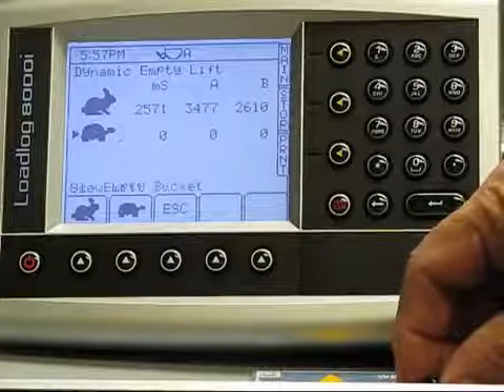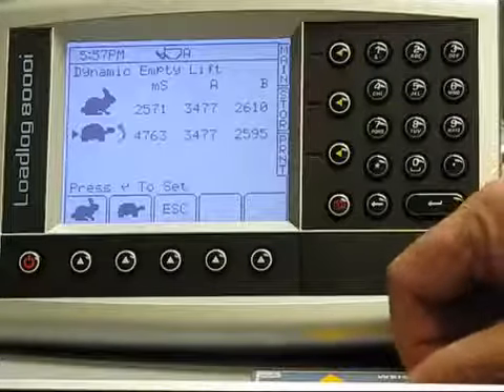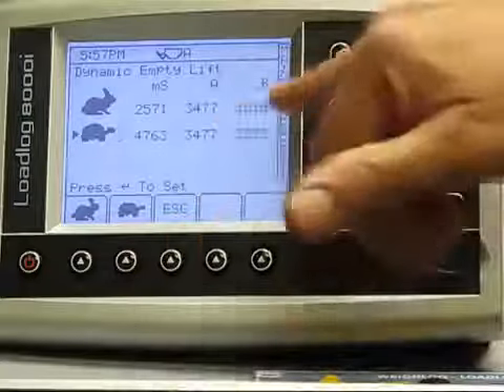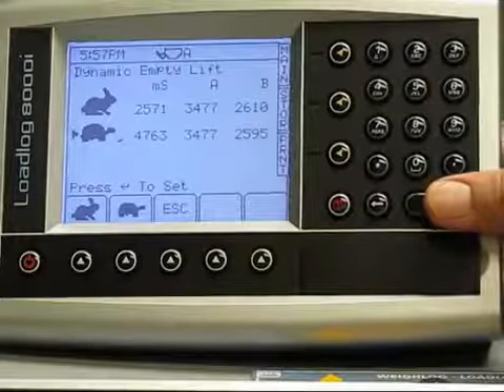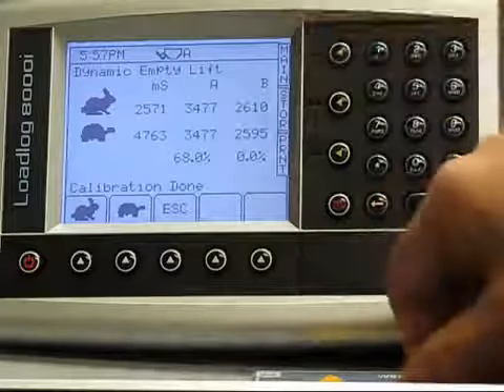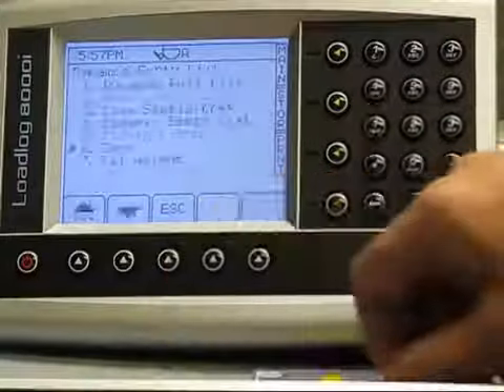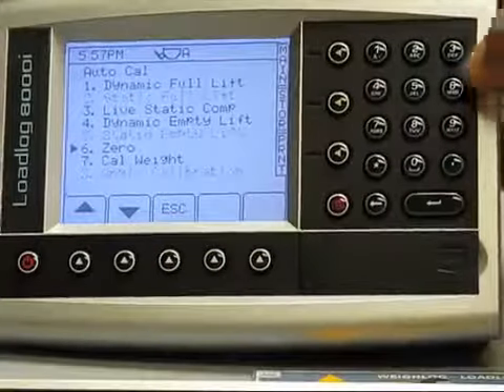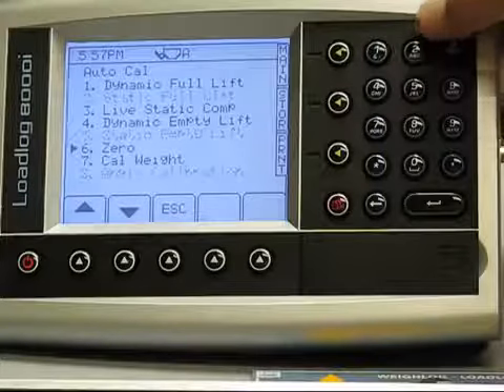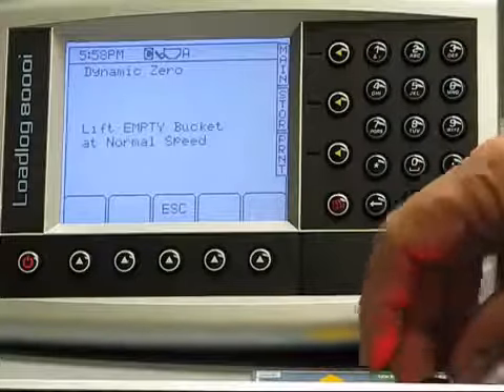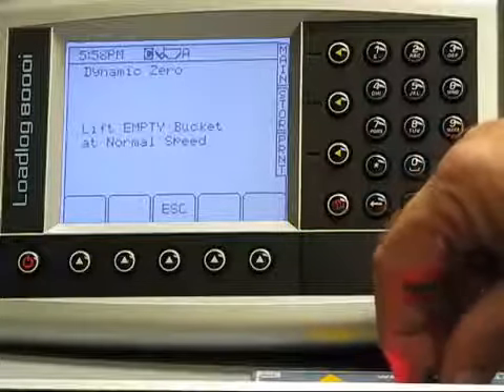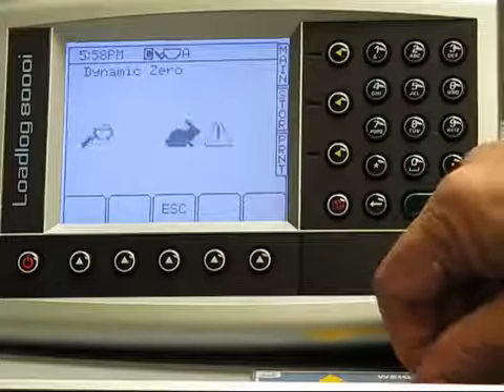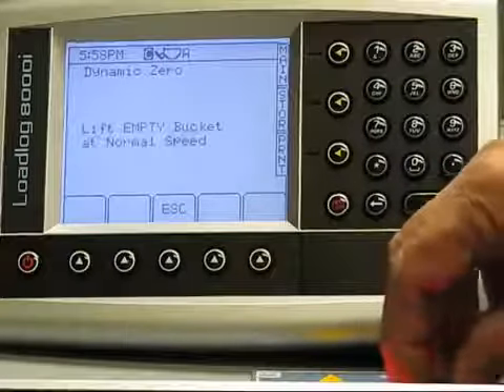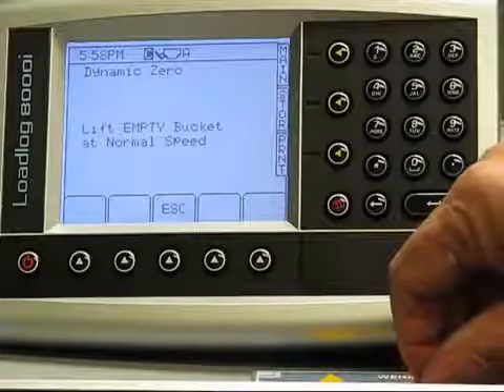Now we do a slow lift, and again the frequencies are going to be the same because we are on a simulated loader here. Press the enter key, and it tells us that the calibration is done. Once we've done that, it will ask for the 0, and the 0 is just that. It's a normal speed 0. So the dynamic 0 would be to lift the empty bucket at quote normal speed. You can tell that I went too fast, and consequently we're going to slow down here a bit, and it took the number and then it's set to 0.